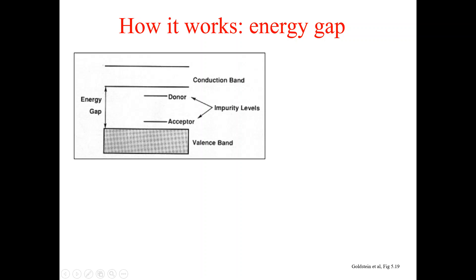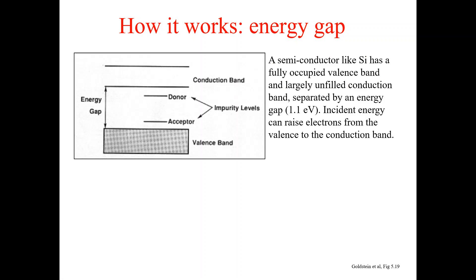Just like we mentioned in the previous lecture, the most common type of EDS detector is the silicon-lithium detector, which means it is mostly a semiconductor detector. Semiconductors like silicon have a fully occupied valence band and a largely unfilled conduction band, separated by an energy gap that is equal to 1.1 electron volt. Incident energy can raise electrons from the valence band to the conduction band.